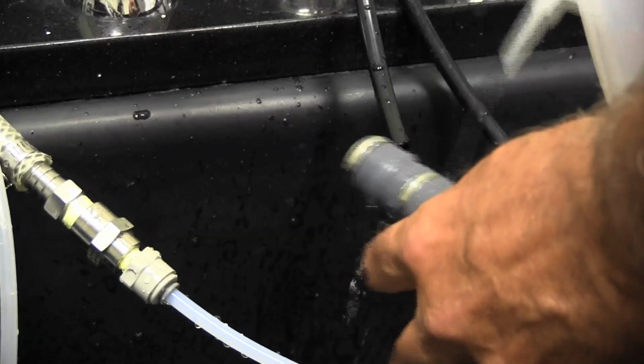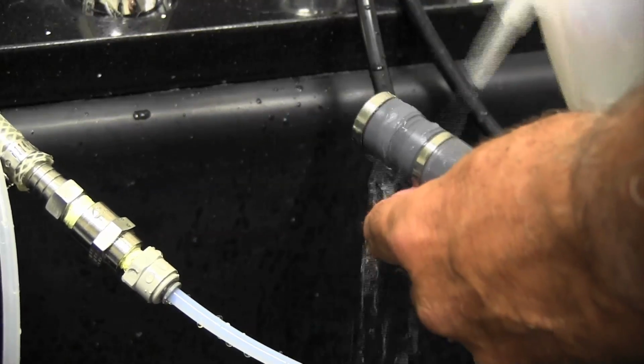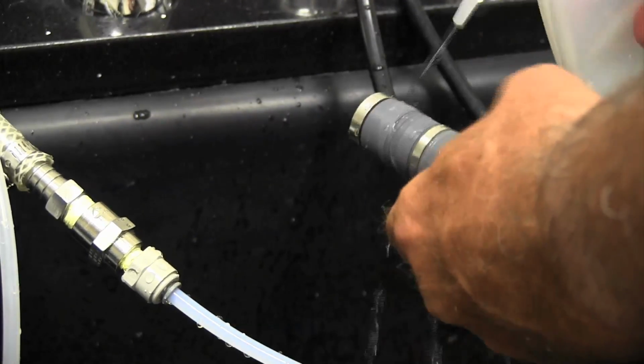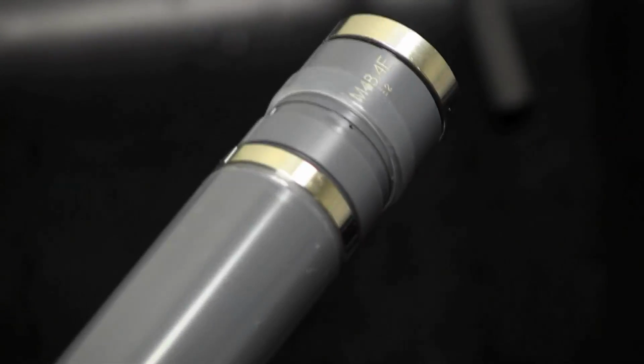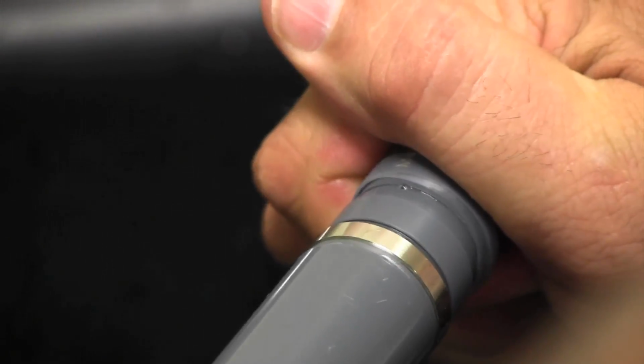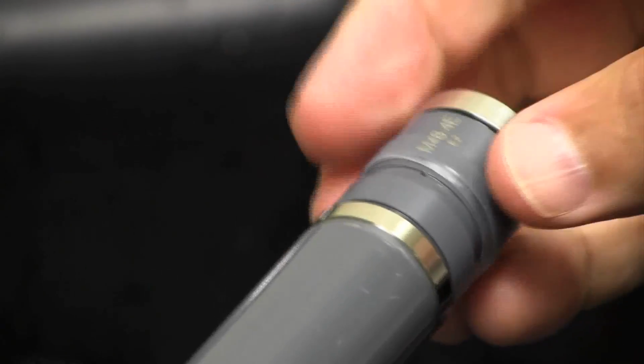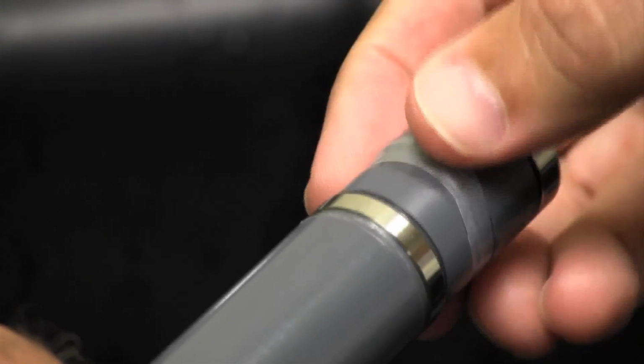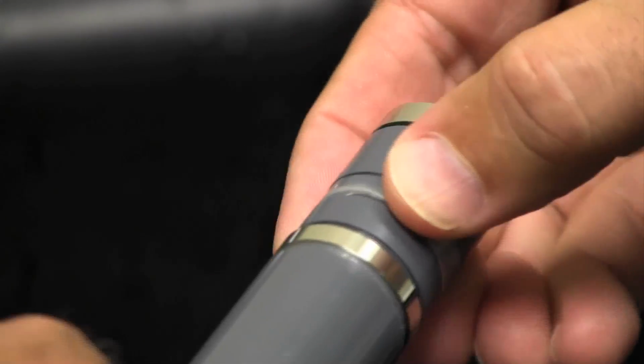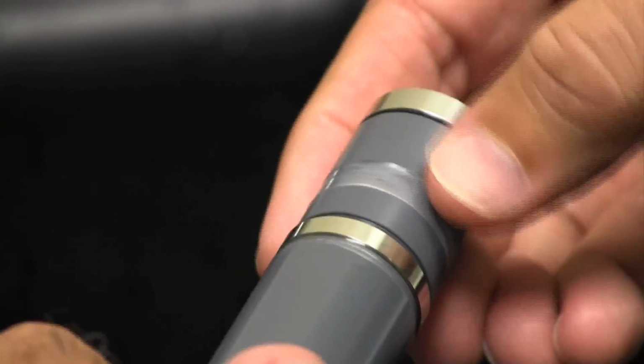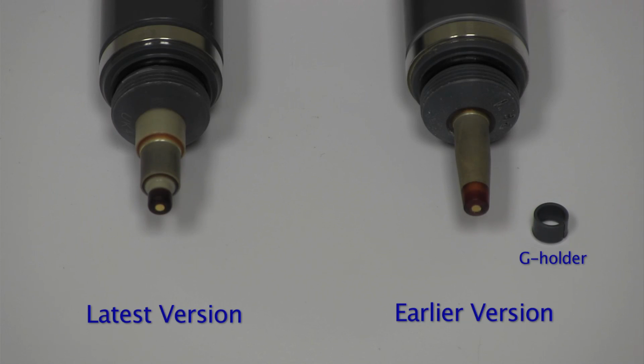Rinse off any excess electrolyte that escapes from the top of the cap and through the vent, and then dry the probe exterior. Now be certain the membrane cap has been hand tightened as far as it will go. Finally, slide the elastic seal into the slotted position over the vent hole, making sure that the seal is seated correctly and not twisted. For some earlier free chlorine probe models, an additional much smaller cap, referred to as a G-holder, was required and included in the kit.